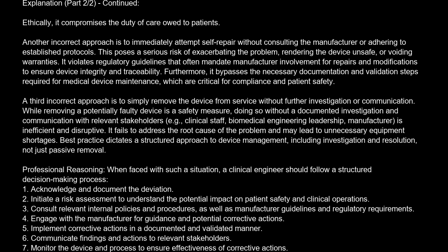This poses a serious risk of exacerbating the problem, rendering the device unsafe, or voiding warranties. It violates regulatory guidelines that often mandate manufacturer involvement for repairs and modifications to ensure device integrity and traceability. Furthermore, it bypasses the necessary documentation and validation steps required for medical device maintenance, which are critical for compliance and patient safety.